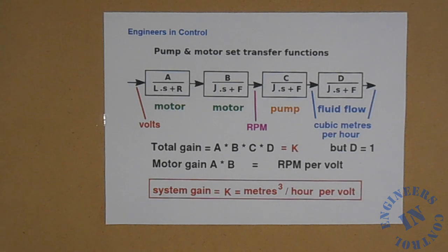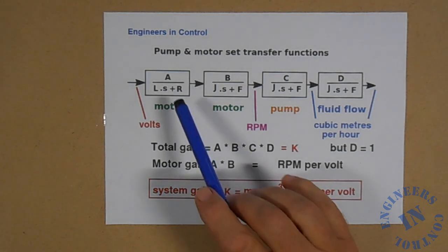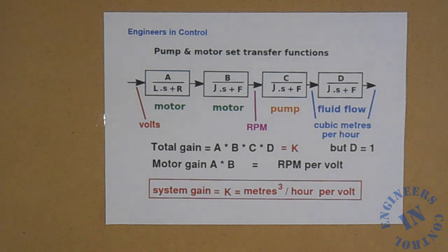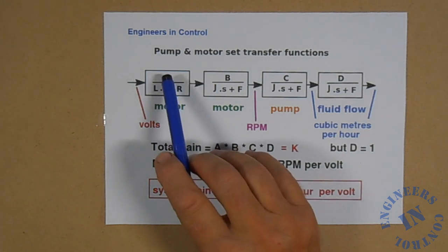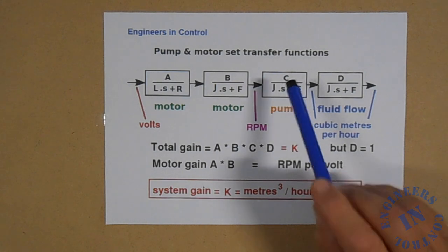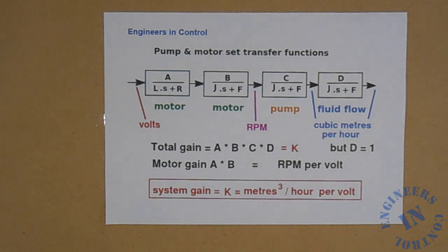Now let us look at the numerator. In fact it is simply a multiplied by b multiplied by c multiplied by d. A times b is just the gain of the motor. The input is in volts and the output is in revs per minute. C is the gain of the pump and converts revs per minute into cubic meters per hour of flow, which is the standard usually used in process plants. And gain d has the same input as the output in cubic meters per hour, and so the gain of d is just one.